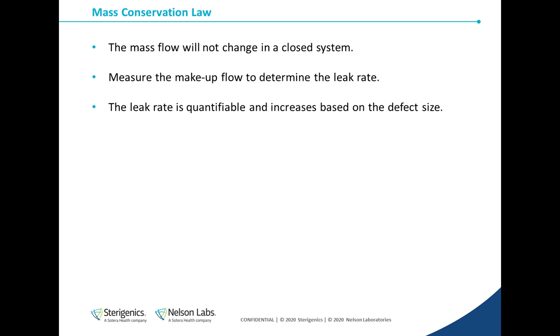Mass extraction is based on the mass conservation law. This law states that mass flow will not change in a closed system. So if you measure the makeup air that's required to hold the vacuum in a closed system, then that will equate to the leak rate. A smaller leak rate would equate to a smaller defect size.